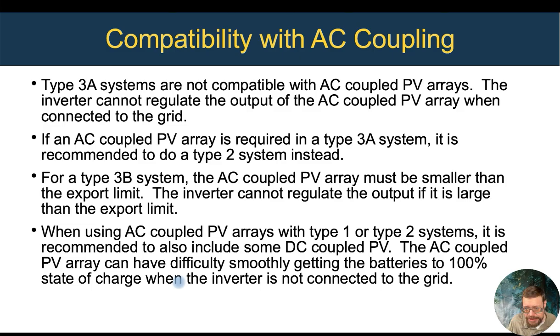Just about all the other systems are compatible with AC coupled PV arrays, either fully off-grid ones or any of the ones where we essentially are allowed to sell unlimited amounts to the grid, either at full retail for net metered ones or limited price for the Type 3 systems. Any of them that we're allowed to sell to the grid can handle an AC coupled PV array up to 12 kilowatts per each of our inverters, and that's limited by the 50 amp input breaker.